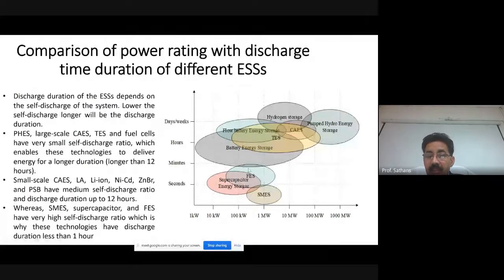Flywheel energy storage goes up to minutes. Then battery energy storage, thermal energy, and compressed air, etc., their discharge time could be from minutes to hours, even days and weeks. Capacity wise, pumped hydro energy storage has the highest capacity, in the range of 1000 megawatts, but its discharge time or duration could be up to 2 weeks. It may last that long, or even hydrogen storage for that matter. But these other systems are going to last only seconds.